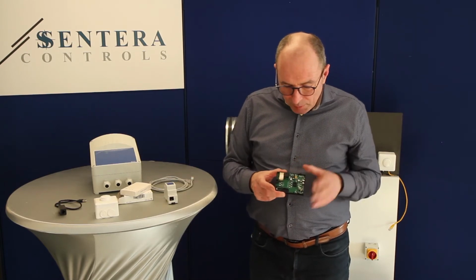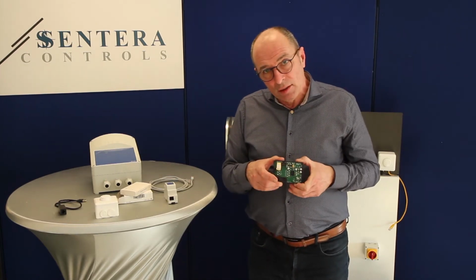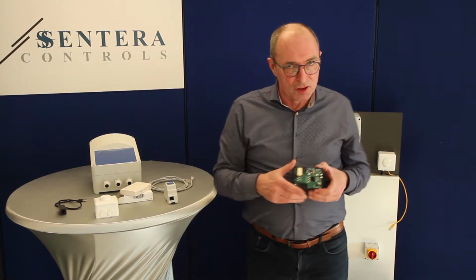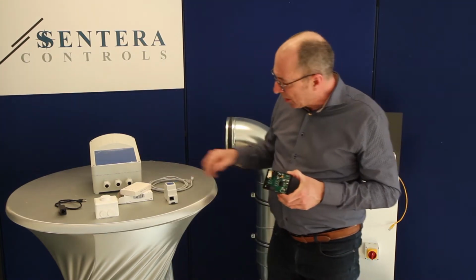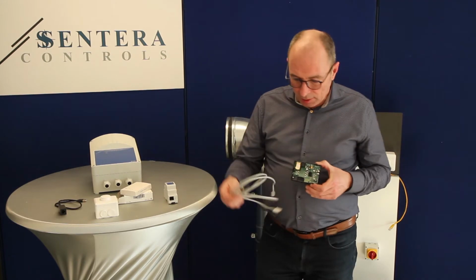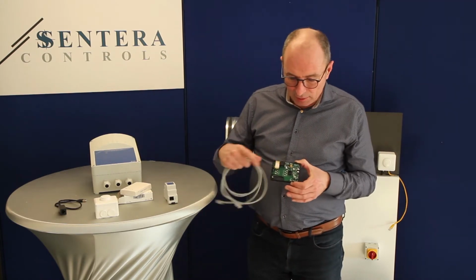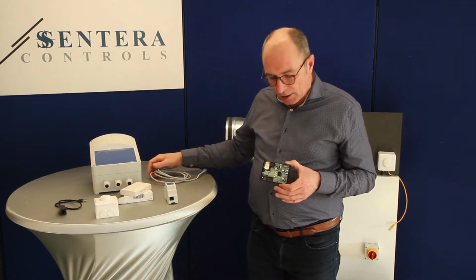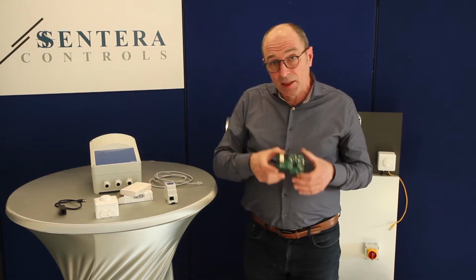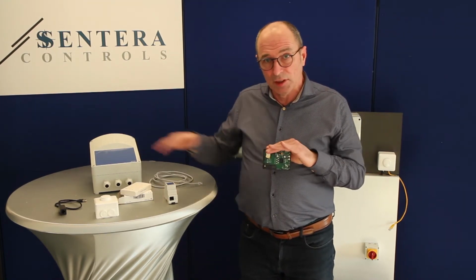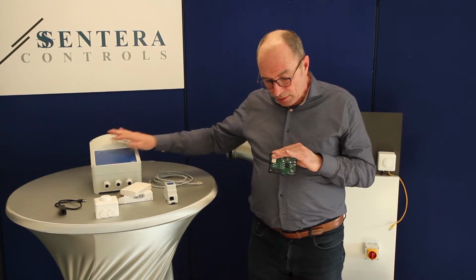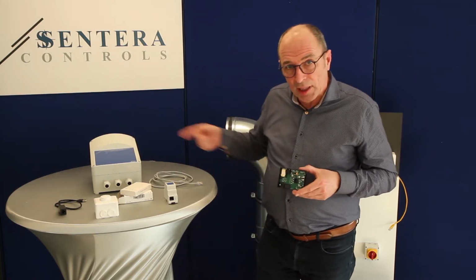In concrete terms, this means that you cannot directly control a fan with this sensor, but that you need to connect them to the transformer controller with a regular network cable, RJ45 on both sides. In this way, the sensor automatically receives its power from the fan speed controller, and there's also data communication between both devices.